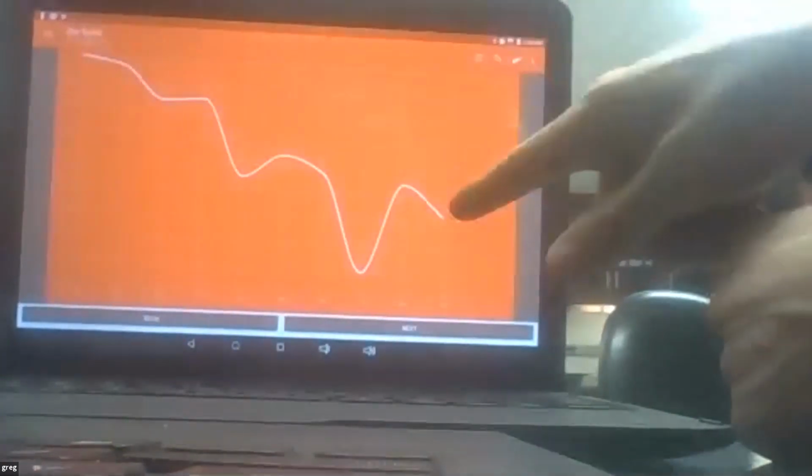It provides you estimates if it's polyphenols or antioxidants. This isn't, but it still gives you the estimates. Gives you all the raw spectral values from 365 nanometers up to 940. Those are all the LEDs that we run. There's 10 points in there. And then it gives you a bunch of raw values and standard deviations and all kinds of detailed stuff people don't want for the most part, and then environmental conditions.